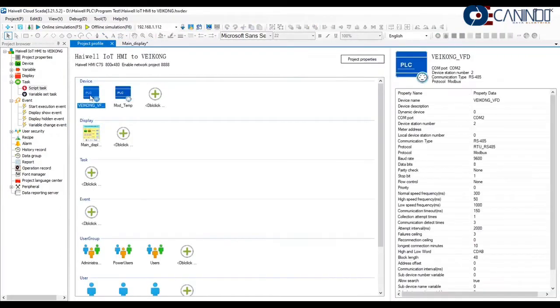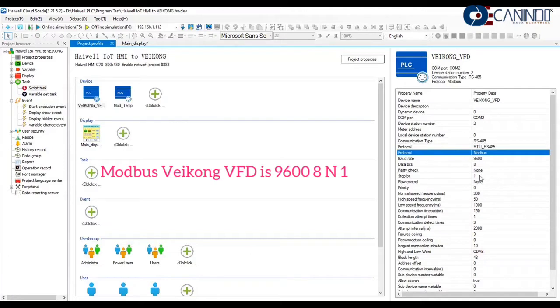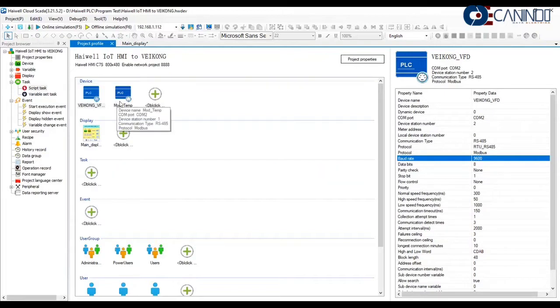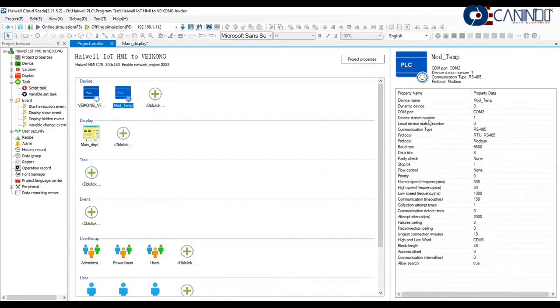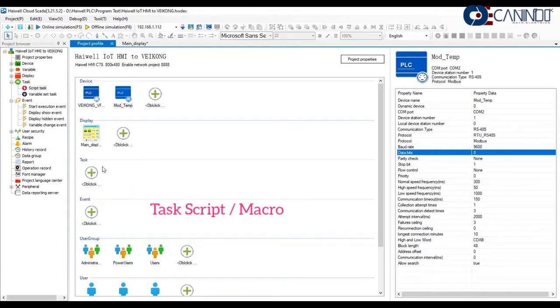For inverter, this is for Veikong inverter, I use modbus, slave ID is 2, this is baud rate, data bit and parity. For temperature control, I use device ID 1, this is baud rate, data bit and parity. Okay, now after that, we make the task script or macro script.